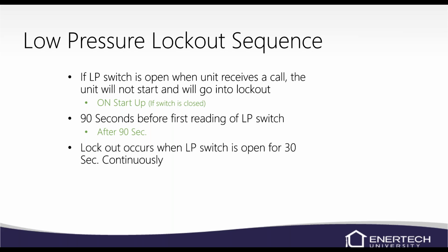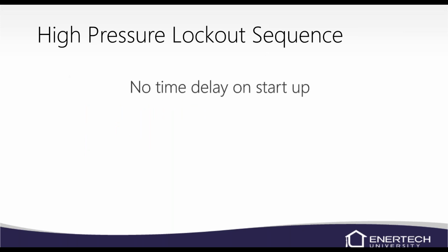So then the low pressure lockout, it has to be open for 30 seconds before it actually faults it out. So as long as it was closed when the Y1 was received, it could be up to 120 seconds before it locks it out on low pressure when it's running. So it can take a little bit of time before it locks it out as long as it was closed on startup. The high pressure switch, again, if it's open when the Y call comes in, it won't start the unit. And anytime that switch opens, it immediately shuts down the compressor. We don't want the compressor to run for 30 seconds if it's at 600 psi or 610 psi. So we'll immediately shut down the system anytime that switch opens up.